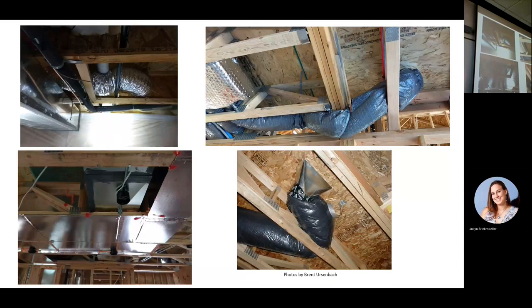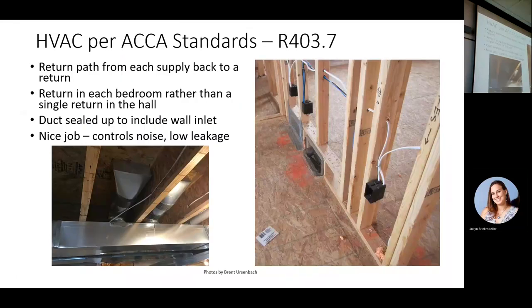How much can you crush a flex duct per the manufacturer? Zero. That was nice. How tight could you bend it? The radius of the duct needs to be the radius of your bend or bigger. No kinking.